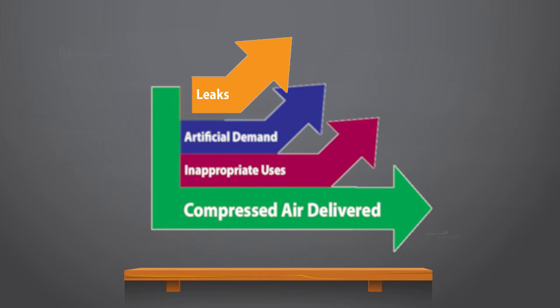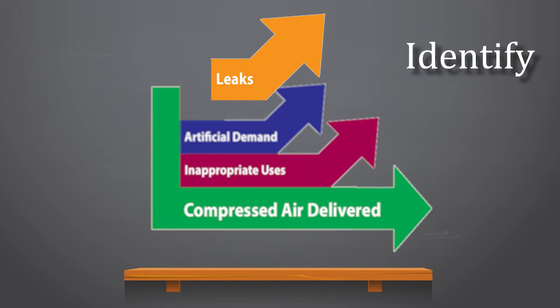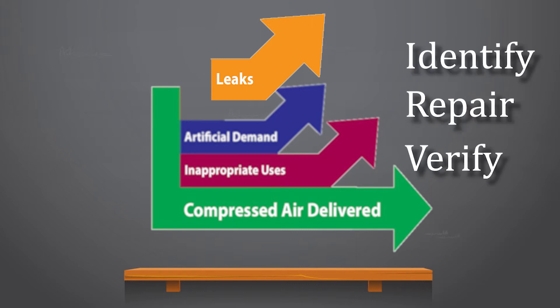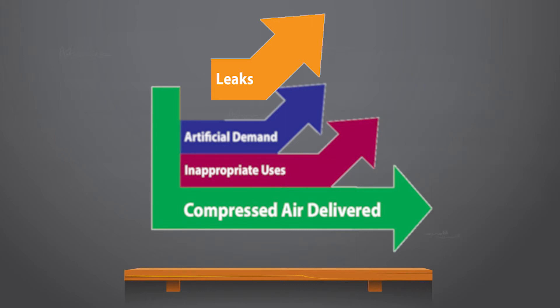Leaks can account for 20% or more of system demands. A leak repair program is helpful to identify, repair, and verify repairs. A formal leak audit performed with an ultrasonic leak detector can identify, quantify, and prioritize leaks to be repaired.